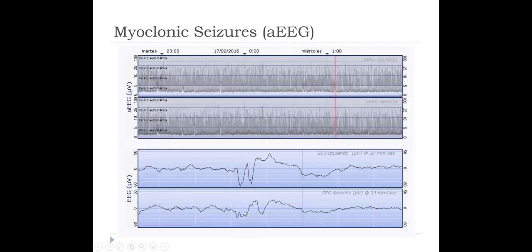Maybe you can see one spike and a slow wave, and in another seizure you can see 2-3 spikes and one slow wave, or only rhythmic slow waves, and it's very different. Remember that the software recognizes 5 waves with the same shape and the same amplitude before it starts the marker.